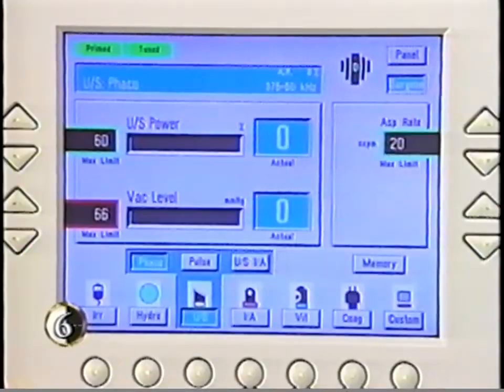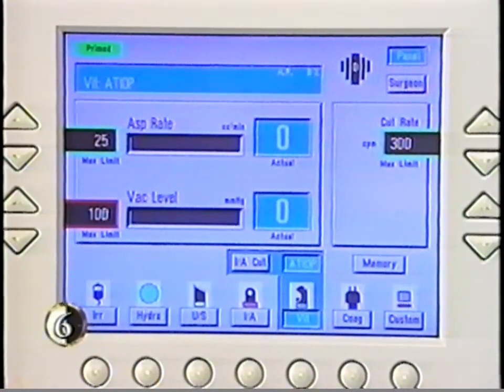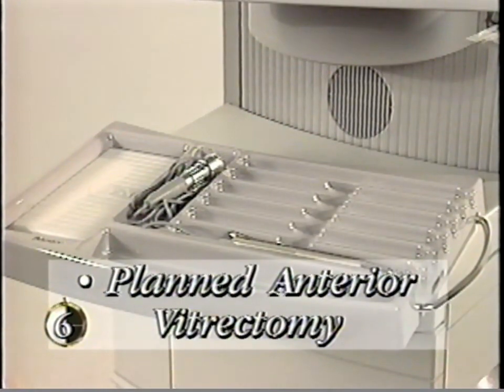If the ATIOP handpiece isn't cutting, confirm that the aspiration port is open and that the irrigation sleeve is not obstructing the aspiration port opening. Be sure the clear ATIOP Luer lock is securely connected to the ATIOP port. If the handpiece still isn't cutting, exchange the ATIOP handpiece and re-prime, or consult the troubleshooting section in the operator's manual. For planned vitrectomy, you must prime the irrigation and aspiration lines before priming the ATIOP handpiece. Refer to the operator's manual for additional setup details.